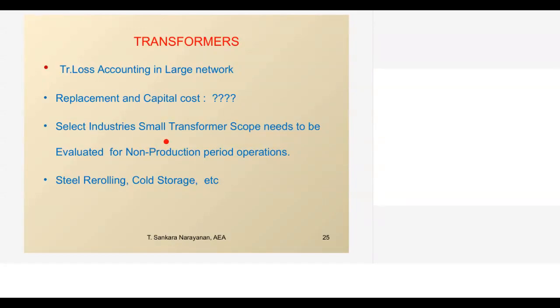Some of the select industries we can go for a smaller transformer, to be evaluated for non-production period operation. Where we are telling, like a small re-rolling mill, you have a 1000 kVA transformer, but the re-rolling mill will not work all the 30 days. They may do rolling operation for 16 days or 18 days. The balance 12 days, the 1000 kVA transformer is operated only for running a small pump and lighting load. So for such type of industry, if the audit is done, one can install a smaller kVA transformer which can be operated during the non-production period.